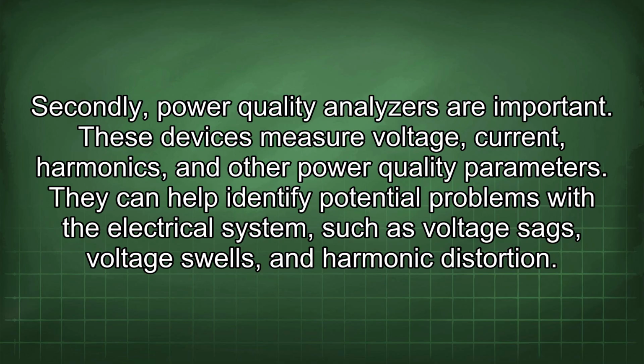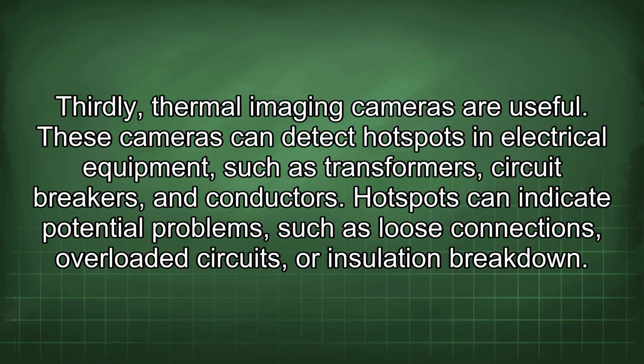These devices measure voltage, current, harmonics, and other power quality parameters. They can help identify potential problems with the electrical system, such as voltage sags, voltage swells, and harmonic distortion. Thirdly, thermal imaging cameras are useful. These cameras can detect hotspots in electrical equipment, such as transformers, circuit breakers, and conductors. Hotspots can indicate potential problems, such as loose connections, overloaded circuits, or insulation breakdown.